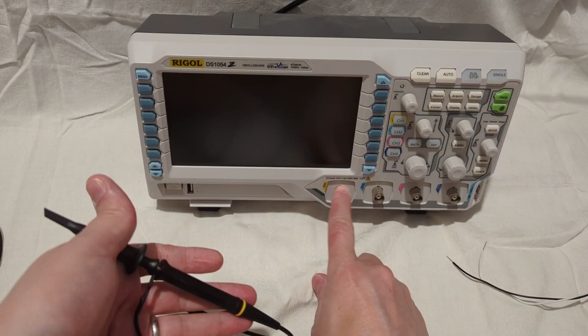Then to put it back together, we just slide this over and it'll pop into place when you push a little hard on it. You can hear it snap. Now, even though the inside of this has a 1 mega ohm termination, whenever this is set to 10x mode, it has a 9 mega ohm resistor in here. So it's actually going to have a total of 10 mega ohms of resistance from the end of this to the scope. So whatever you're measuring is going to get loaded with 10 mega ohms typically in this mode.